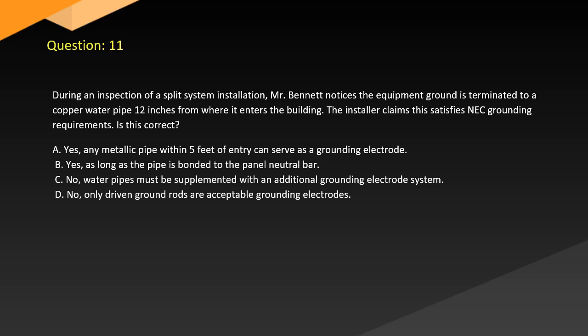Question 11. During an inspection of a split system installation, the inspector notices the equipment ground is terminated to a copper water pipe 12 inches from where it enters the building. The installer claims this satisfies NEC grounding requirements. Is this correct? A. Yes, any metallic pipe within 5 feet of entry can serve as a grounding electrode.